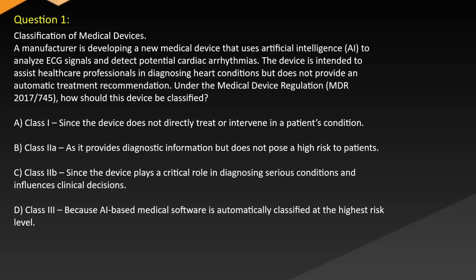Question 1. Classification of medical devices. A manufacturer is developing a new medical device that uses artificial intelligence (AI) to analyze ECG signals and detect potential cardiac arrhythmias. The device is intended to assist healthcare professionals in diagnosing heart conditions but does not provide an automatic treatment recommendation. Under the Medical Device Regulation MDR 2017-745, how should this device be classified?